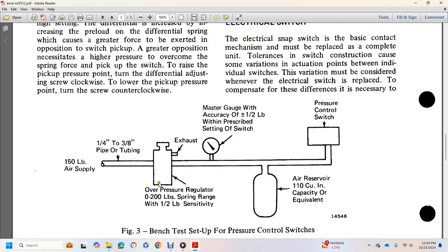And shows a bench test setup of the pressure control switch. Pressure control switch. Air reservoir 110 cubic inches in capacity, equivalent master gauge accuracy of half a pound plus or minus with the prescribed setting of the switch. Exhaust overpressure regulator 0 to 200 pounds. Spring range of half a pound, sensitive to the 1/4 inch to 3/8 inch pipe or tubing, 150 pound air supply.